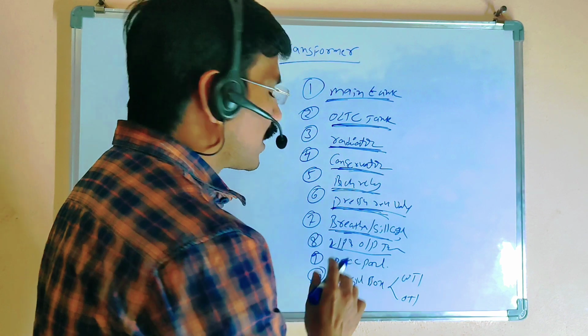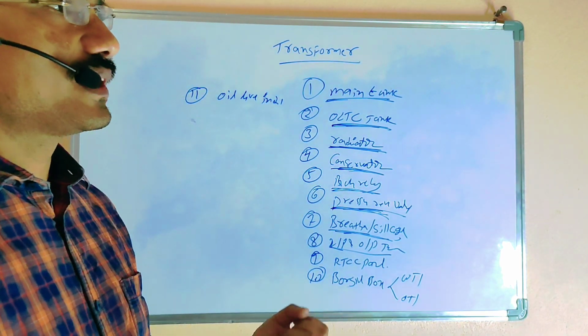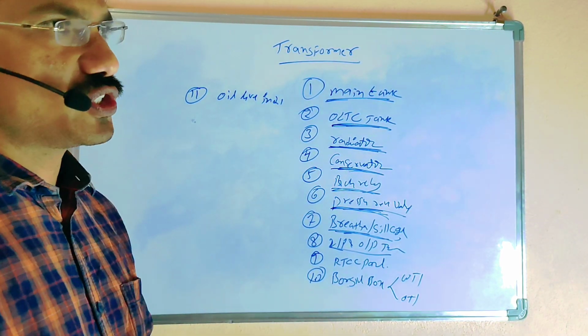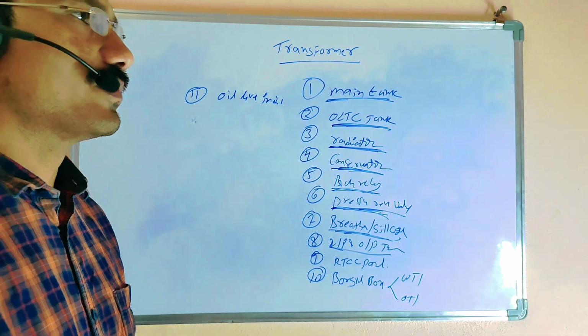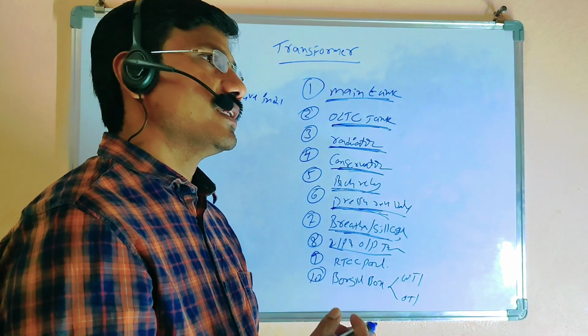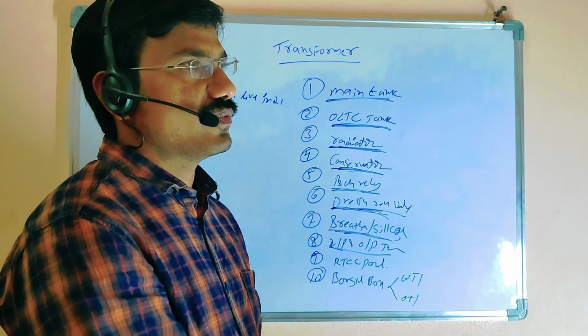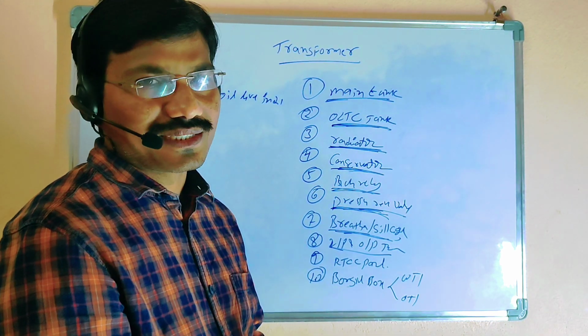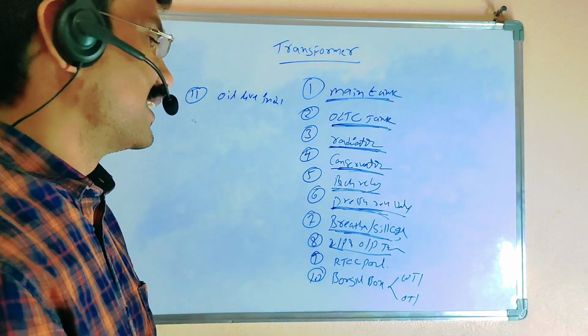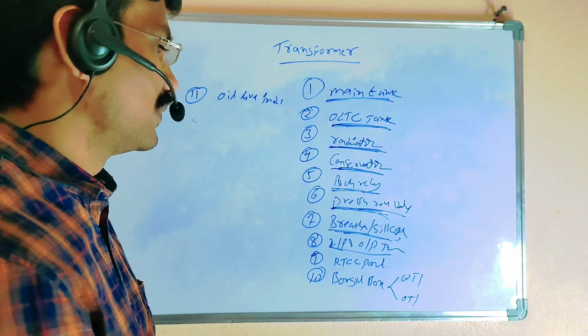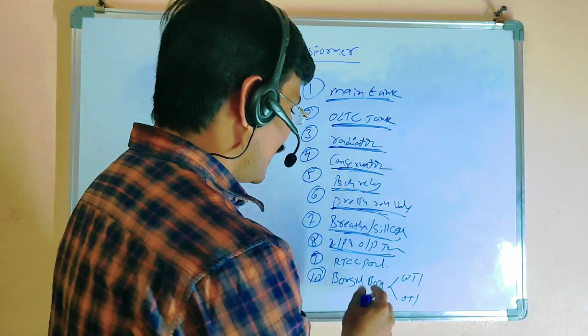After that, if we go for the input and output terminals: for the input terminals, if it is a distribution transformer, meaning step down transformer, input 33 kV we are connecting. The cable is coming from the VCB. Output we connect to the LT side, LT kiosks. Those are the terminals.